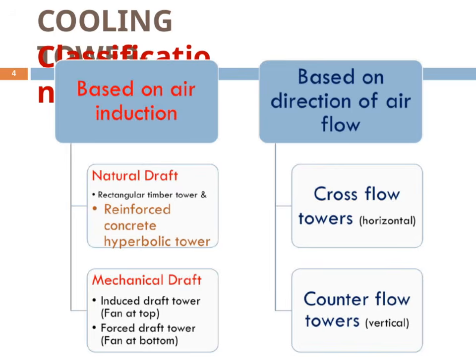Cooling towers can be classified in two different ways. The first classification is based on air induction. In this category, cooling towers are divided into natural draft towers and mechanical draft towers. Natural draft towers include reinforced concrete hyperbolic towers that use natural airflow. Mechanical draft towers use fans and are divided into induced draft towers, where the fan is at the top, and forced draft towers, where the fan is at the bottom. The second classification is based on airflow direction. These include cross-flow towers with horizontal airflow and counterflow towers with vertical airflow.